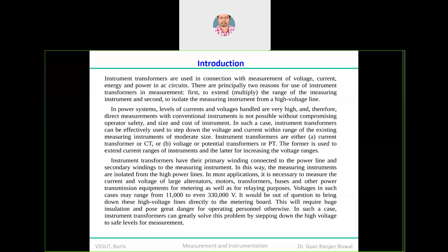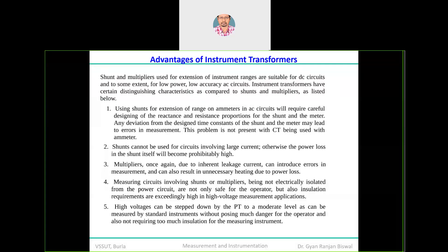To ensure insulation quality meets industry and electrical power standards, you would require a very high degree of insulation, which ultimately compromises on cost and may make the whole operation very expensive. Instrument transformers greatly solve this problem by stepping down the high voltage to a safe range — bringing the current and voltage level down to such a low level that it can be directly interconnected with your measuring device. The instrument transformers have distinguishable characteristics compared to shunts and multipliers.